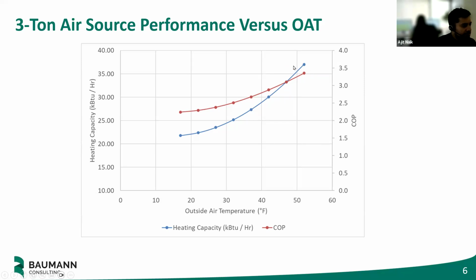So, on a cool but not too bad day, say in the low 50s, we have an operating efficiency of 3.3, 3.4. That means for every 1 unit of electricity we put in, we're getting 3.3, 3.4 units of heat out. Pretty good. At the same time, we get a capacity of almost 37 kilo-BTUs per hour, right?